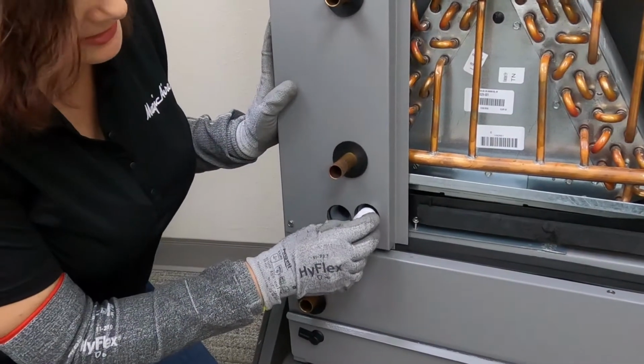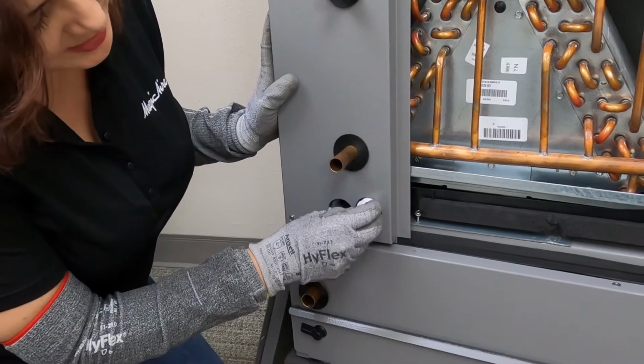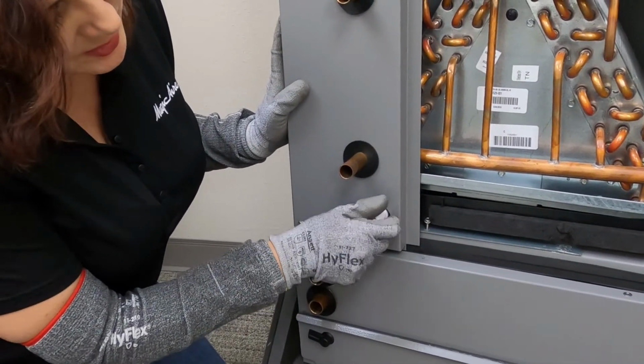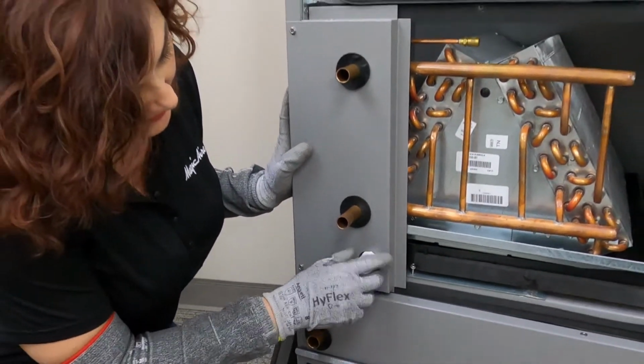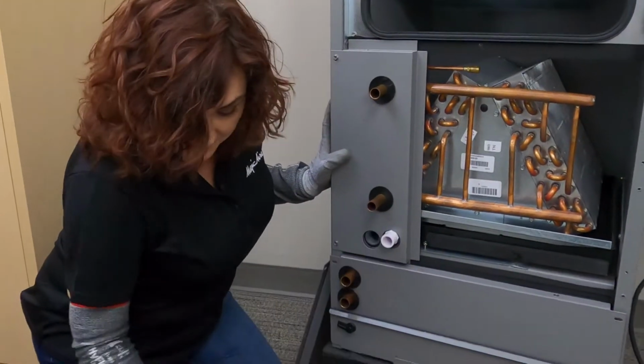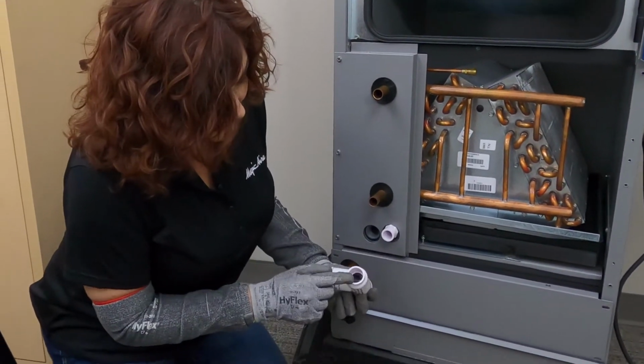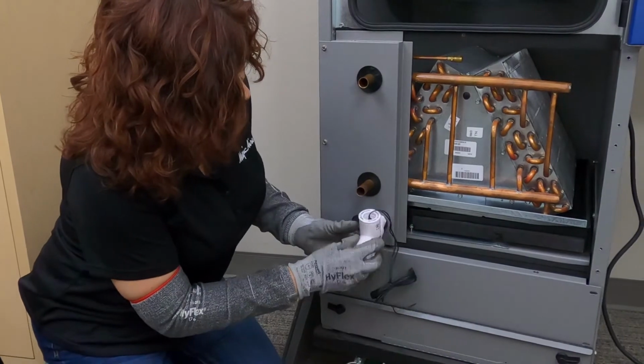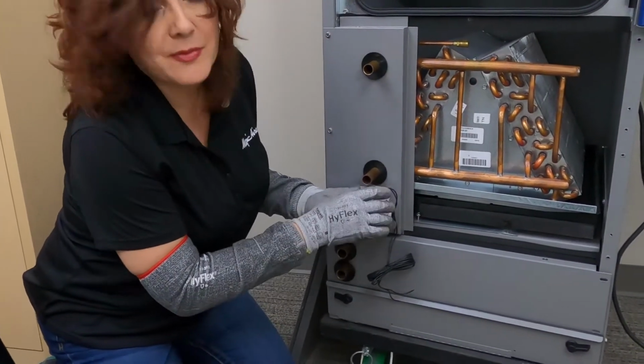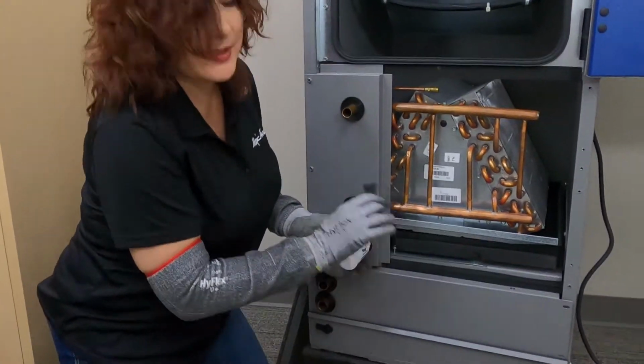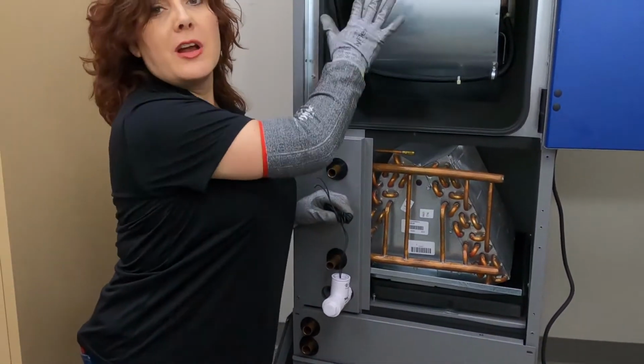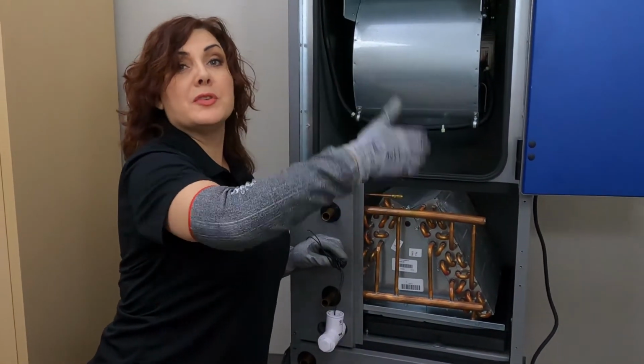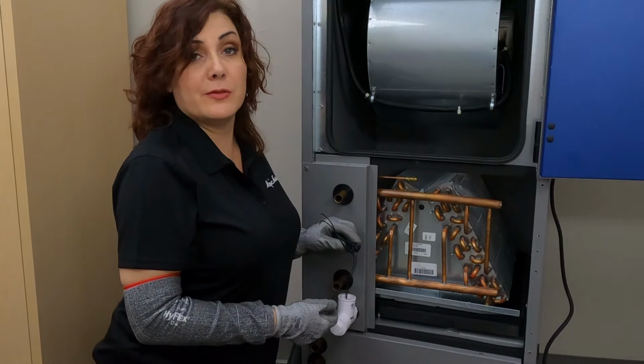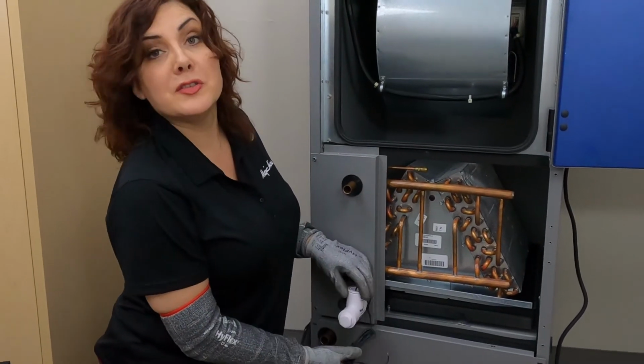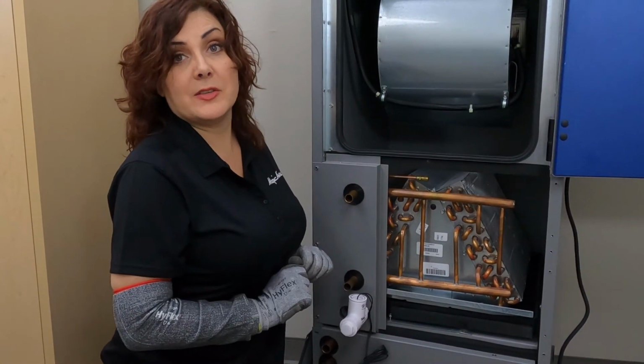You may or may not have the condensate overflow switch. If you don't have one, you might want to install one. It goes on the secondary drain. It has a float inside, so when this is halfway full, this just slides on. When it's halfway full, it'll send a signal to the electrical, and you can shut off the unit. That way you're not producing condensate that's going to flood the floor. And that'll let you know that you need to clean the condensate drain.